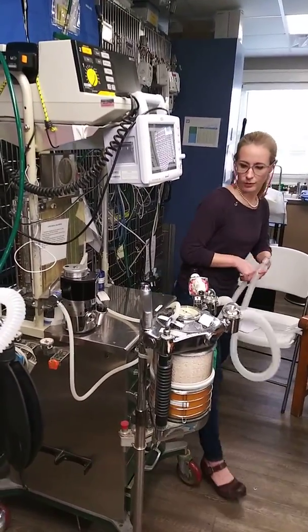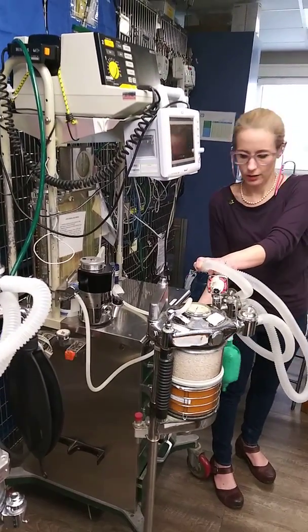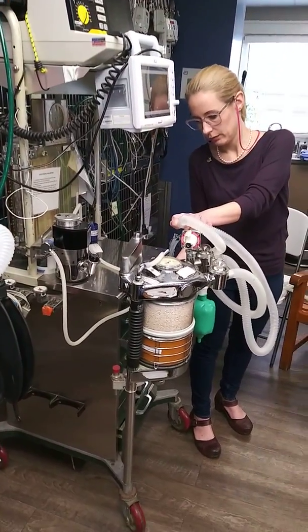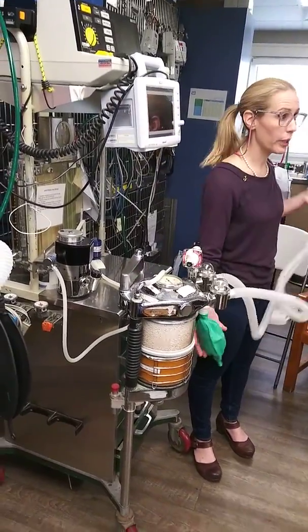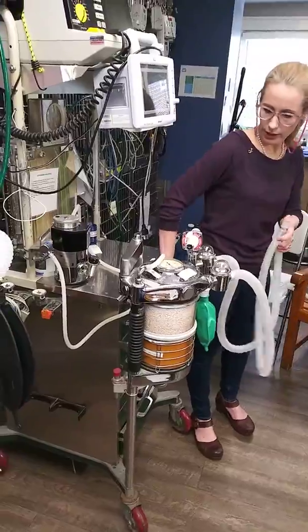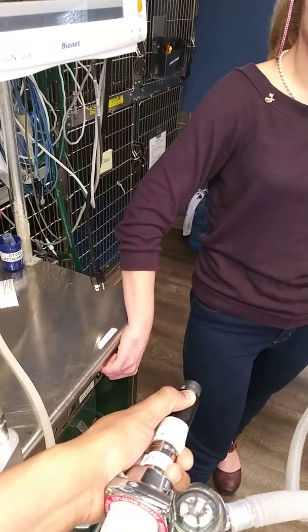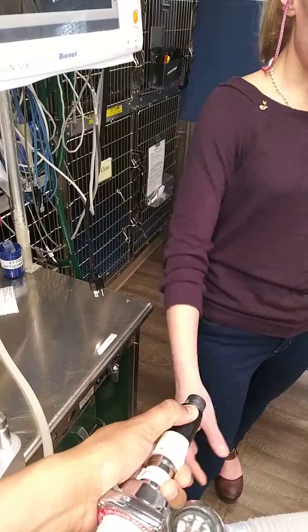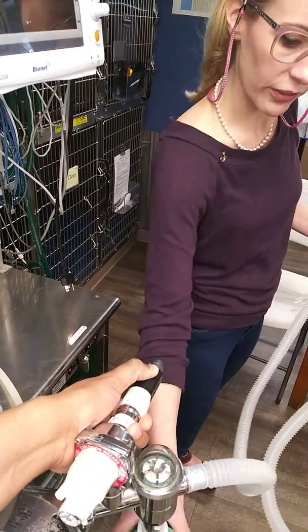So, I guess I should show the circuit test. What is this little bag called? This is called the rebreathing bag. Okay, so I'm actually going to test the circuit right now. This was the beginning of the pop-off occlusion saga of 2016. Okay, this is how you actually check the circuit. So you see as Ryan is pushing this closed, I should have gone over that earlier.